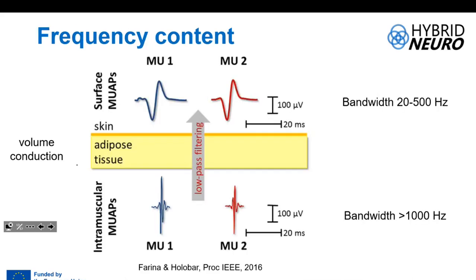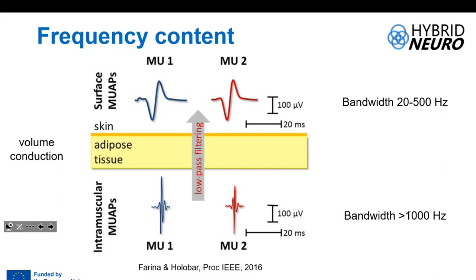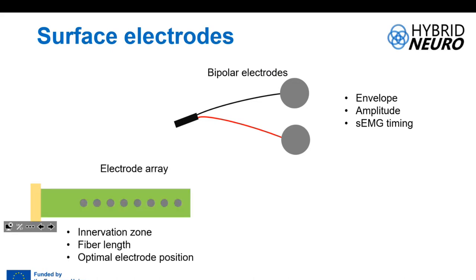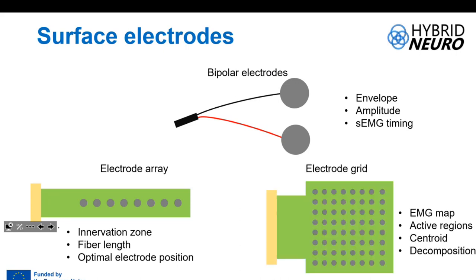These slides are mainly dedicated to surface signals because we will have another workshop dedicated to invasive recordings. The electrodes presented in the next slides are for surface EMG recordings. The classical configuration is bipolar electrodes — you place two electrodes and calculate the difference in voltage between the two points. You can also use an array of electrodes, such as eight detection points in a linear configuration, or bidimensional grids, for instance an eight-by-eight configuration.